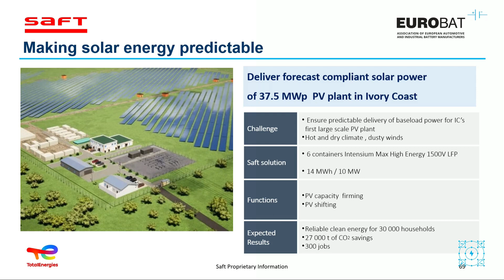What the battery does here is capacity firming. This means it ensures that the power injected from the PV to the grid corresponds to the forecasted power in half-hour steps. The battery isn't big enough to shift power from day hours to evening hours - that's not the purpose. But it firms, ensuring that what is planned is really delivered.